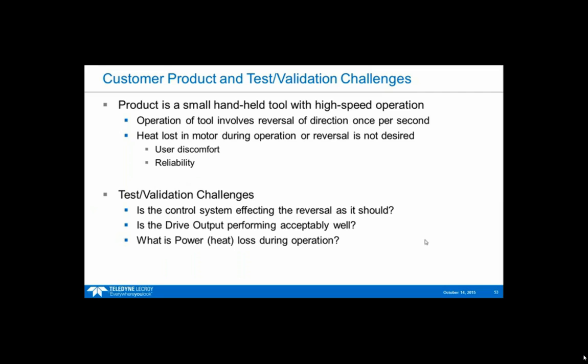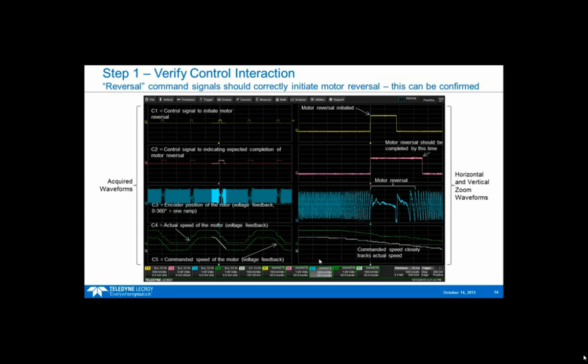And so basically the test and validation challenge here is trying to understand how the control system is interacting with the motor and the drive as it should, and is the output of the drive performing well, and also understanding the power and heat loss during the operation. So what we have here is signals. These 4 signals on the left are the actual full acquisition. We're dealing with a 5-second acquisition, or 500 milliseconds per div times 10 divisions. Sample rates are reasonably low here.